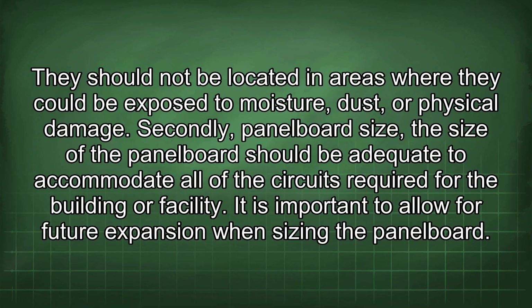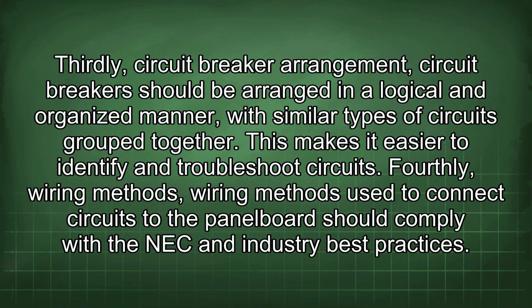Secondly, panel board size. The size of the panel board should be adequate to accommodate all of the circuits required for the building or facility. It is important to allow for future expansion when sizing the panel board. Thirdly, circuit breaker arrangement. Circuit breakers should be arranged in a logical and organized manner, with similar types of circuits grouped together. This makes it easier to identify and troubleshoot circuits. Fourthly, wiring methods.